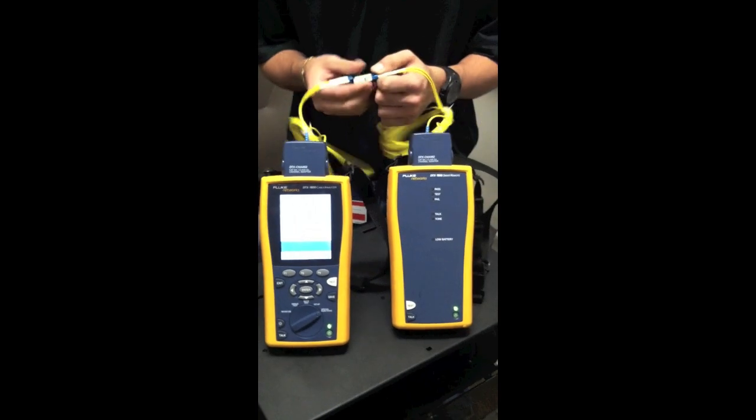So once we have our reference set we're going to disconnect from our coupler. Put this to the side. And if we ever disconnect using one jumper reference never disconnect from the source side. And same thing with the Corning light meter. You never want to disconnect the cable from the source always from the meter side.